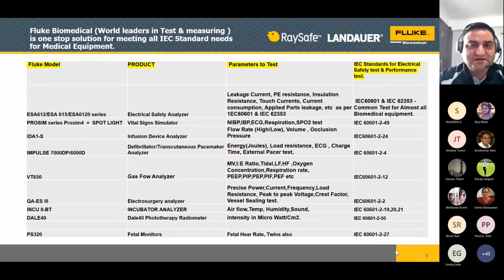Similarly, as we discussed just now, Dr. Jitendra also discussed gas flow analyzers, ventilators. You have to see minute volume, tidal volume, oxygen concentration, respiration rate, PEEP, inspiratory pressure, expiratory pressures, all those things you have to check. Suppose we are delivering 100% oxygen, if it is only going 60%, you are not giving enough oxygen to the patient. Similarly, there is the electrosurgical unit. Then incubator analyzers are there for incubator testing, warmer testing, phototherapy radiometers. You have seen phototherapy machines. So on the extreme right, I have mentioned all the standards.